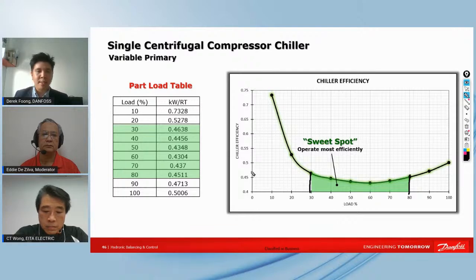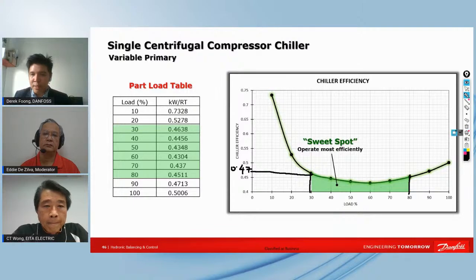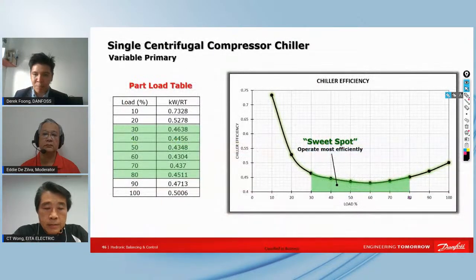Let's say the owner says, "End user, okay, if I buy this kind of chillers, I would like to operate at 0.47." And the second question they will ask us is, "I want to take full advantage of this. So what do I have to do?" Then they say, "I want to operate most of the time at 0.47, which is the sweet spot." And that means it only has to operate between 30 and 80% capacity. Above that, it will compromise the efficiency, right?